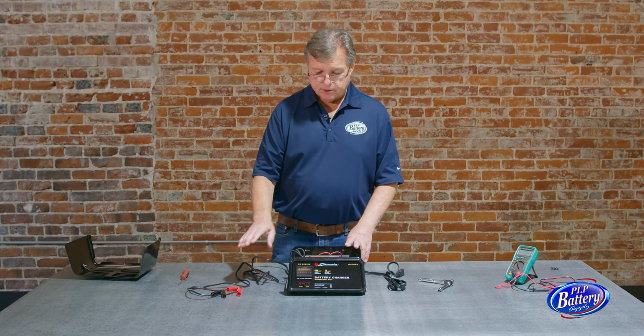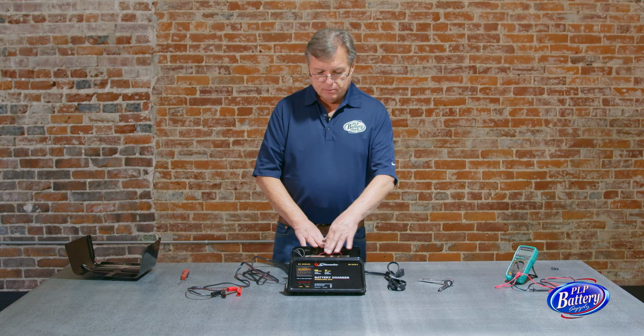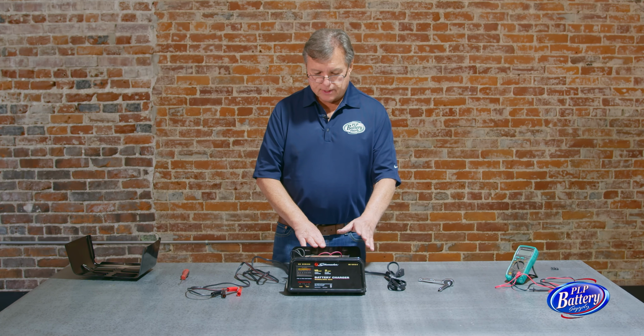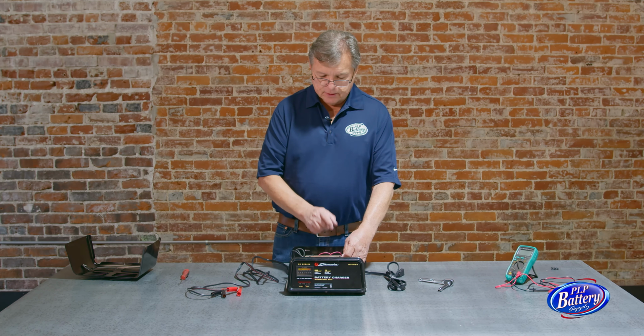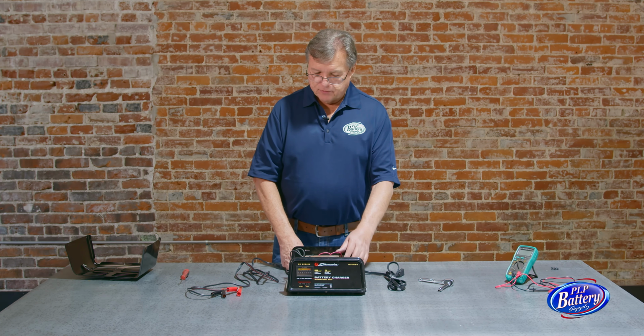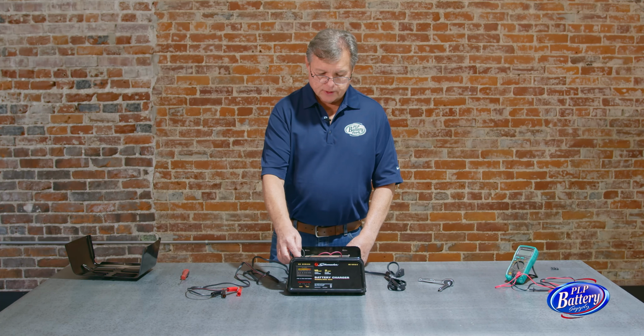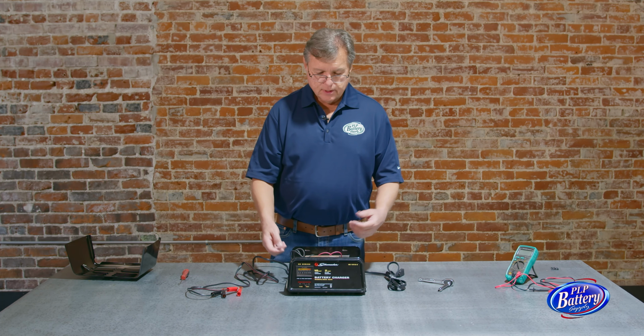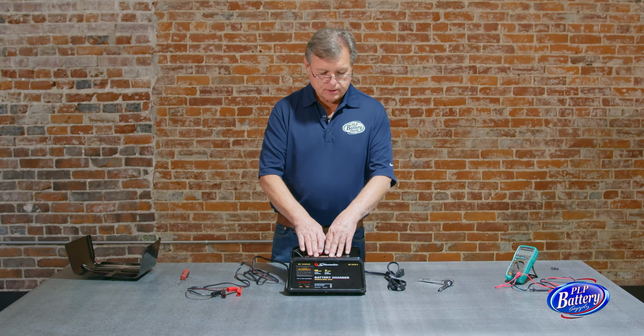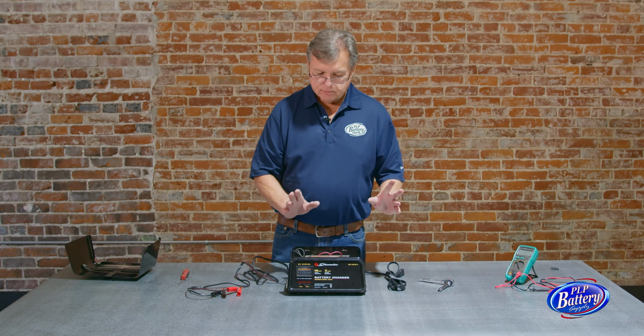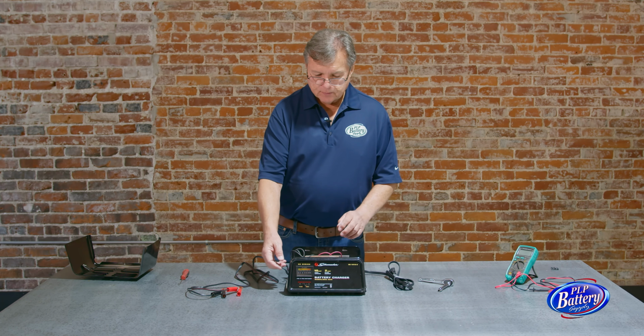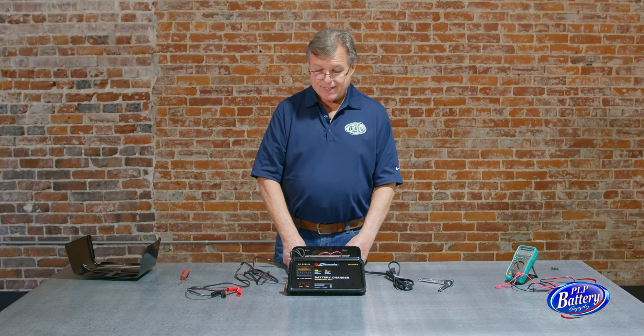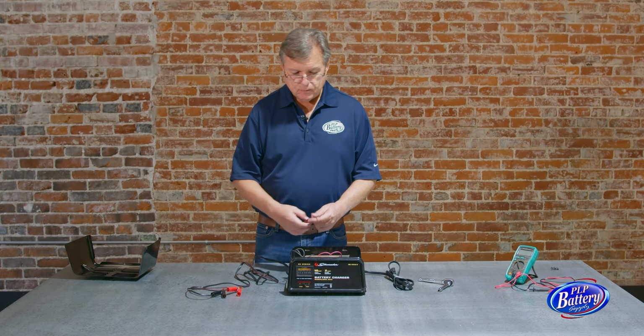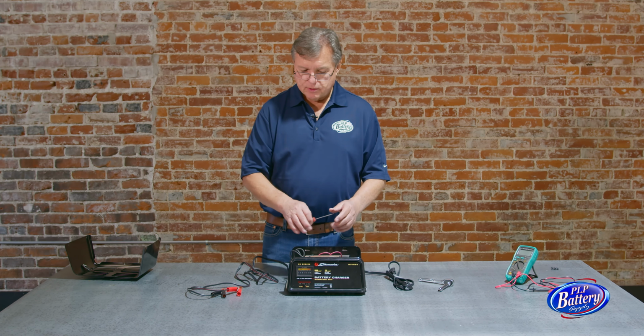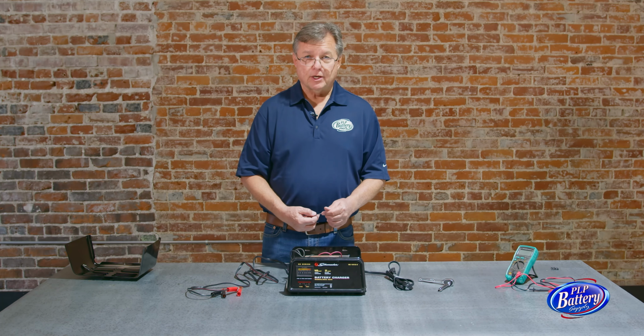So, continuity at the clamps. Check those clamp connections. If you have to get inside, make sure that the thing is humming, that the AC transformer is working, and then your next thing is going to be look at the rectifier. If all that stuff is good, then you're looking at meter, DC breaker, and that's about it. If you're not getting any hum out of the transformer, again, the AC cord and maybe the switch. That's it. These are not terribly complicated. So if you get all that stuff repaired, everything's working, this charger is going to be just like brand new.